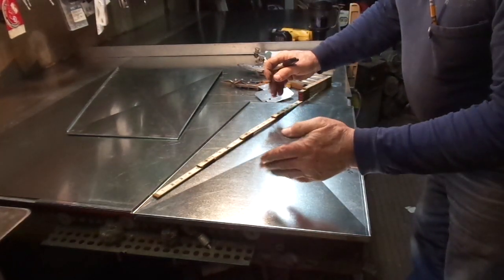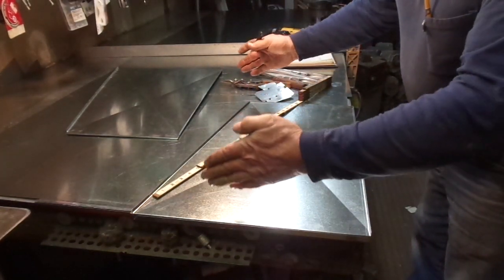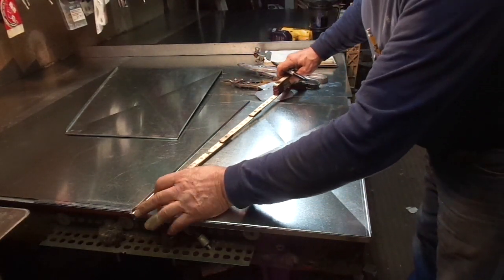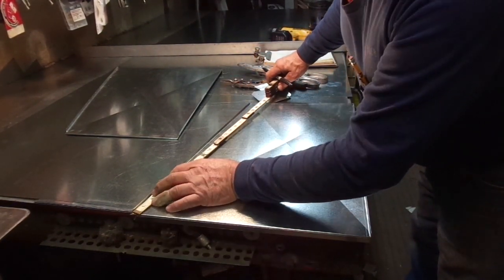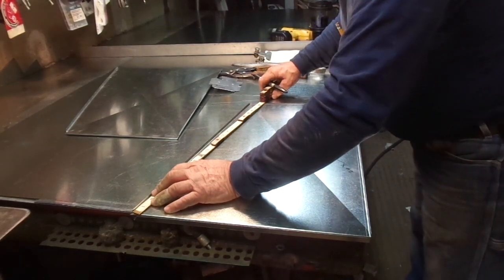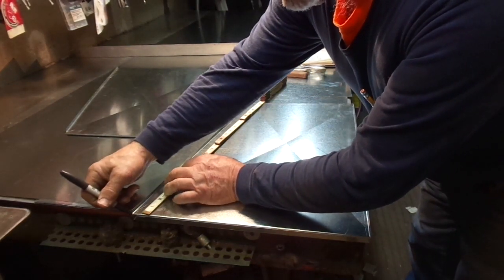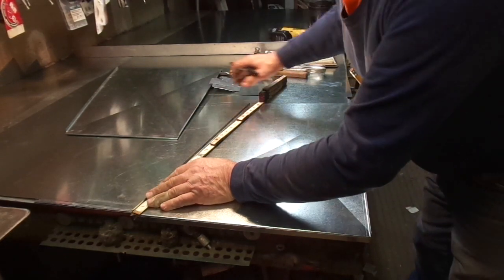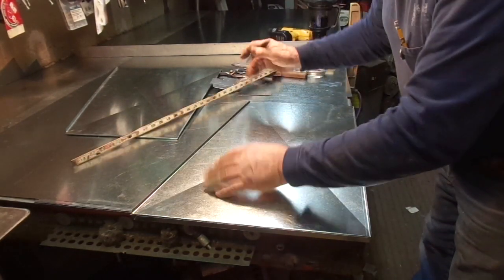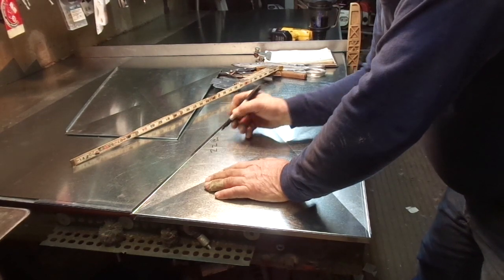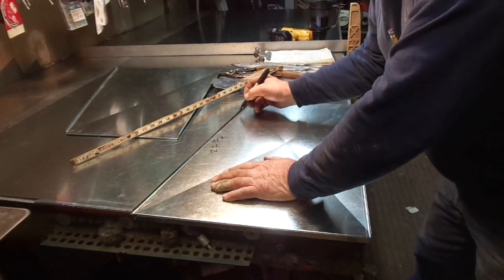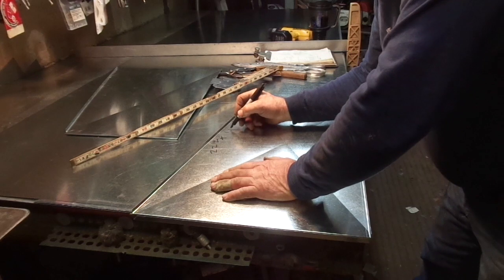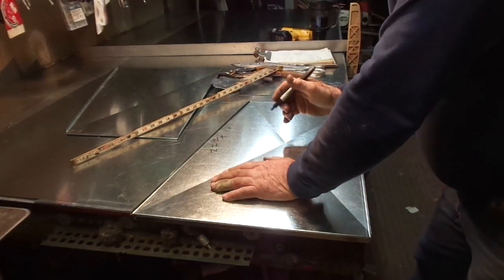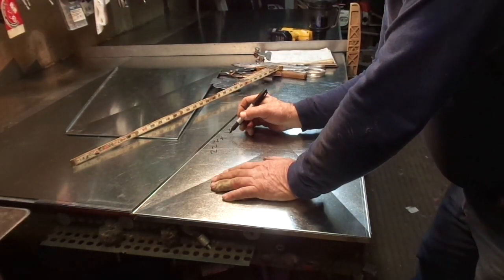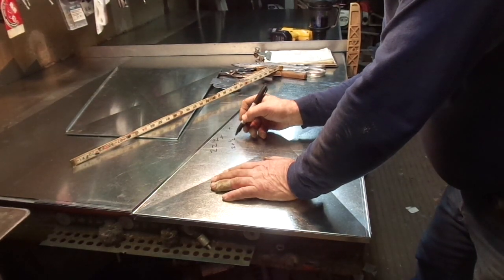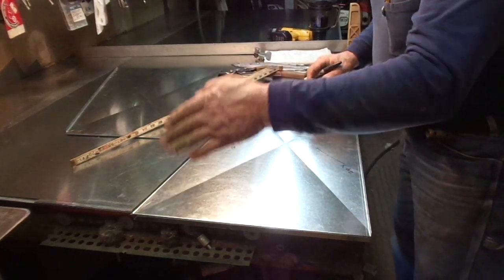So we're going to have to allow for the Pittsburgh locks and then put the taper on it, and then go ahead and lay that out. Now the length on this one's going to be a little longer, and it's a little more tricky measuring the angles, but again, go from your scribe line where your two notches intersected to where the two notches intersected, we gain a half an inch. This is 22 1/2 in between the lines, so it's plus one for the drive tabs, plus one for the half inch double hem. So that's 22.5 plus two, which is 24 1/2 by whatever that width needs to be.